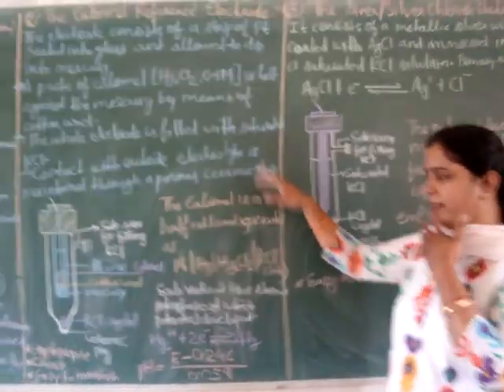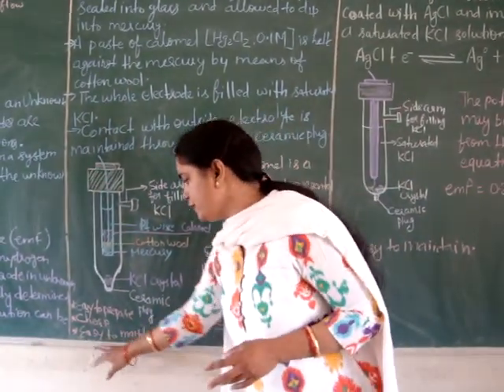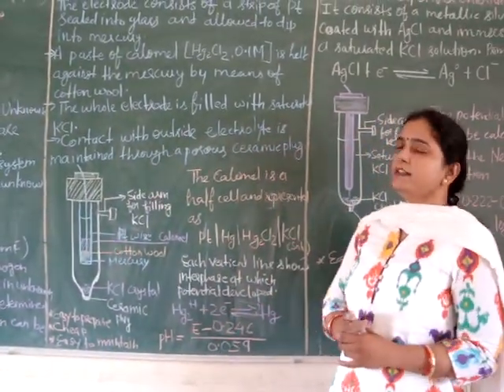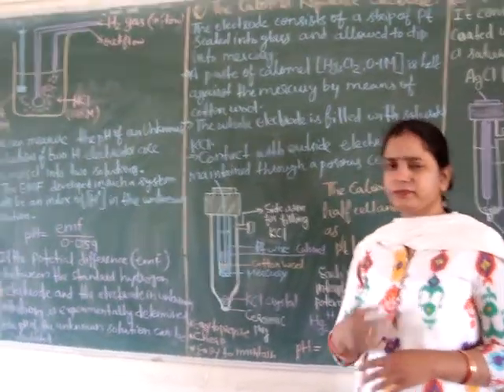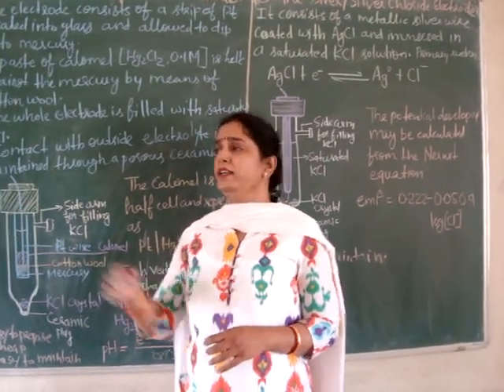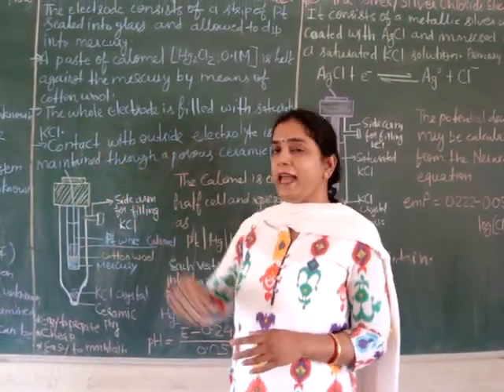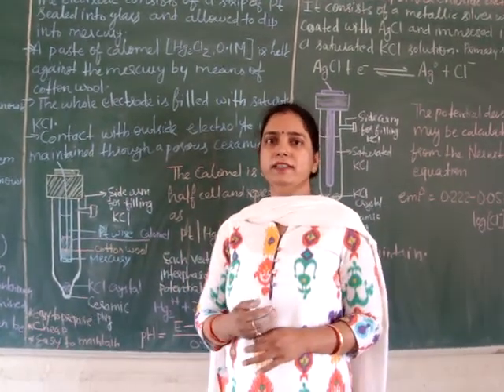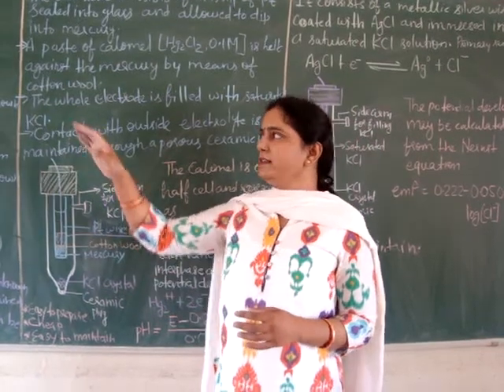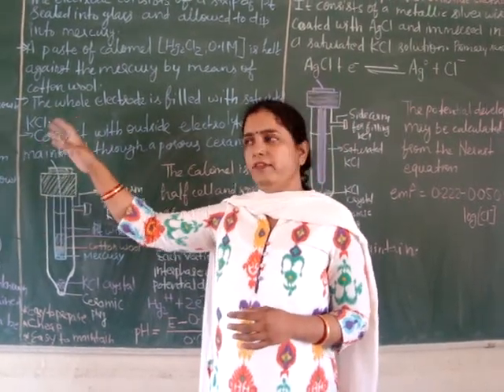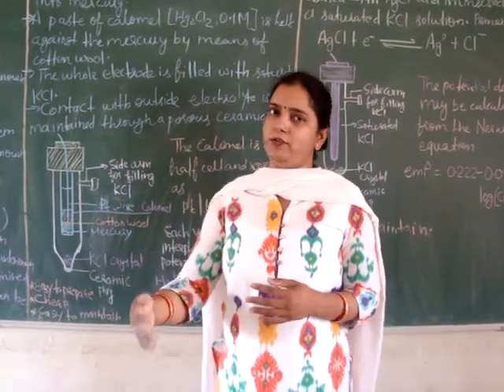The calomel reference electrode is very easy to prepare and it is very cheap and easy to maintain. That is why it is generally used as a reference electrode, whereas the hydrogen electrode is not easy to maintain because hydrogen gas must flow at constant pressure, which is very difficult to maintain. So it is rarely used, but it is used to determine the electrode potential of other reference electrodes.